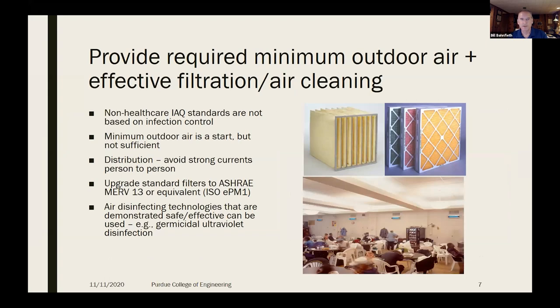Now what do we do with HVAC systems? We should provide at least the amount of outdoor air that's required by minimum standards. This is essential for controlling all sorts of indoor air contaminants. It's also a good baseline, although not sufficient, for controlling infection risk. As far as air distribution is concerned, avoiding strong currents that are going to extend close contact transmission is important.